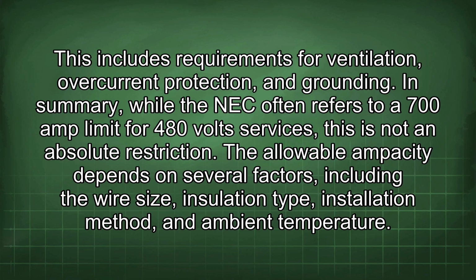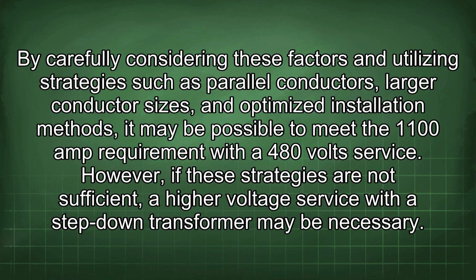In summary, while the NEC often refers to a 700 amp limit for 480 volt services, this is not an absolute restriction. The allowable ampacity depends on several factors, including the wire size, insulation type, installation method, and ambient temperature. By carefully considering these factors and utilizing strategies such as parallel conductors, larger conductor sizes, and optimized installation methods, it may be possible to meet the 1100 amp requirement with a 480 volt service. However, if these strategies are not sufficient, a higher voltage service with a step-down transformer may be necessary.